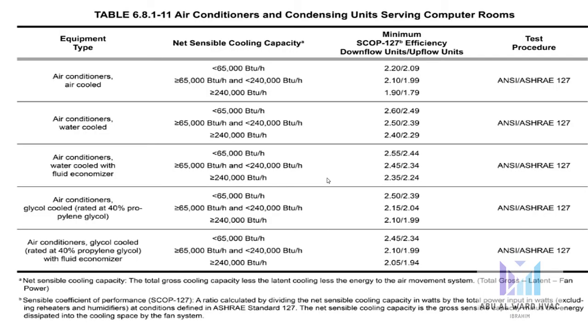Another diagram from ASHRAE shows the differences of different types: air-cooled type and water-cooled type, and water-cooled with the fluid economizer, and the glycol-cooled, which is water-cooled type also mixed with the glycol, and the efficiency, net sensible cooling capacity, which is very much less in the glycol type compared to the water-cooled type and the air-cooled type.